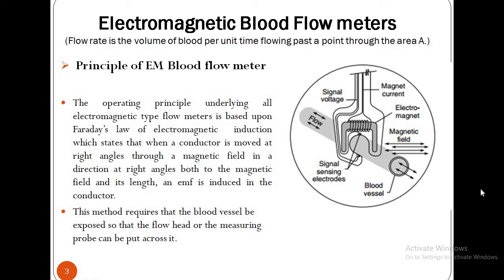First is the electromagnetic blood flow meter. The most commonly used instrument for measurement of blood flow is the electromagnetic blood flow meter. With this type of instrument, blood flow can be measured in intact blood vessels without cannulation and under conditions which would otherwise be impossible. But this method requires that the blood vessels be exposed so that the flow head or the measuring probe can be put across it.